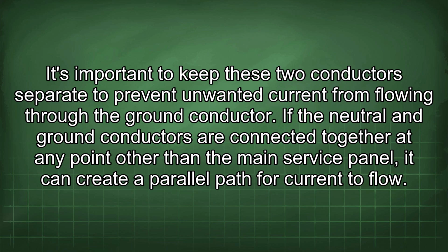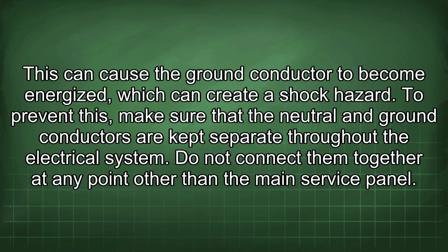If the neutral and ground conductors are connected together at any point other than the main service panel, it can create a parallel path for current to flow. This can cause the ground conductor to become energized, which can create a shock hazard. To prevent this, make sure that the neutral and ground conductors are kept separate throughout the electrical system. Do not connect them together at any point other than the main service panel.